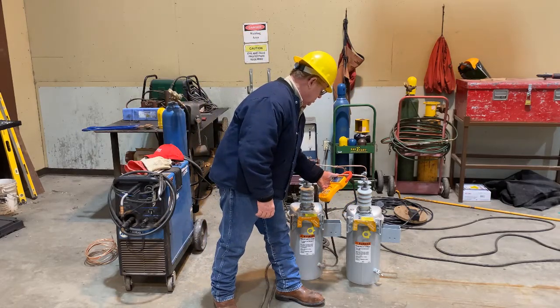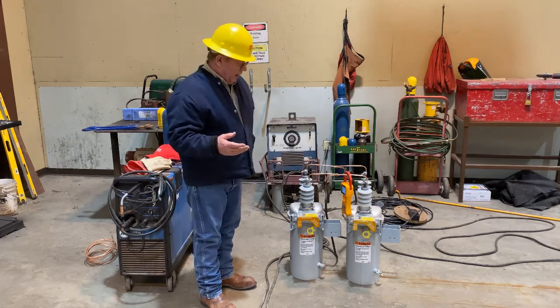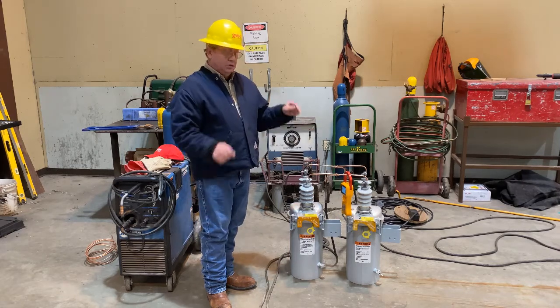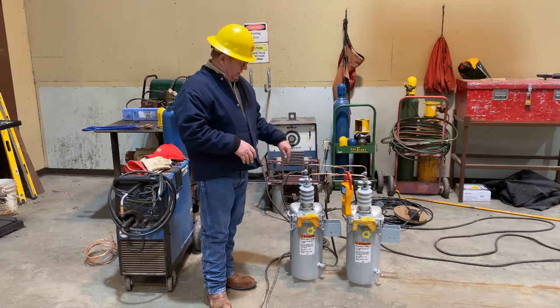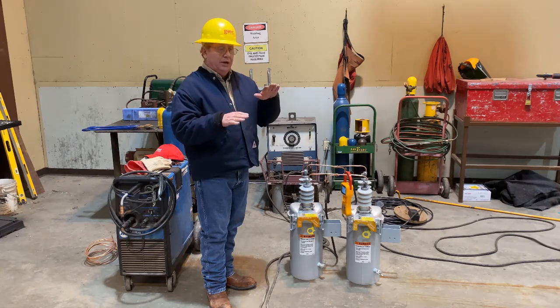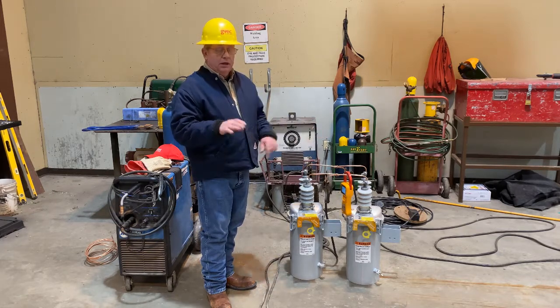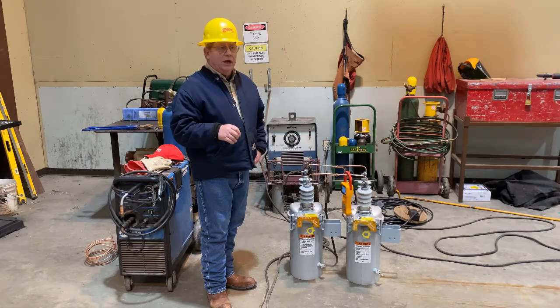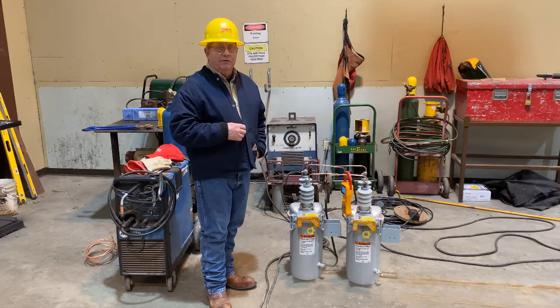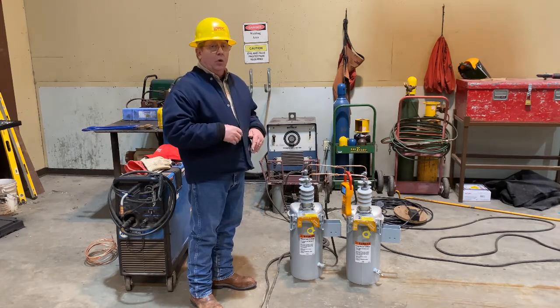The Fluke shows that we pushed almost 450 amps through that recloser. Now we're going to set up another demo as part of this one. We're going to take one of the reclosers and drop it in a bucket of ice, and we're going to take the other one and use a tank heater to elevate the oil temperature as high as we can get it — so we can create a dramatic temperature delta. In Central Texas, we have drastic temperature changes where wintertime will be in the 20s and summer can be 105 degrees, and we want to see how that affects oil circuit reclosers.